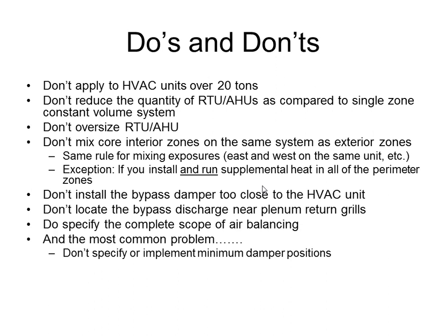One do that we want to stress again is specifying the complete scope of air balancing. You want to tell your air balancer that they need to do all of those requirements that we listed on the previous slides, and you want to make sure that they're out there when the controls contractor's out there so they can coordinate the proper control.